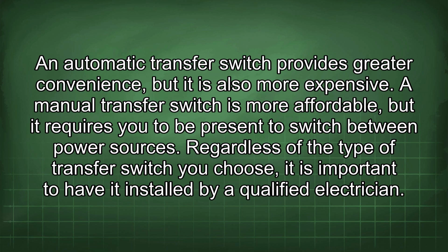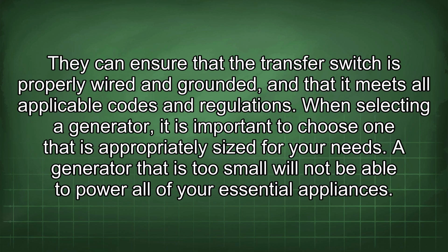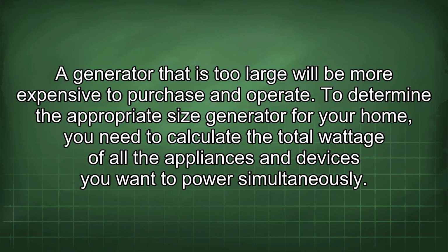Regardless of the type of transfer switch you choose, it is important to have it installed by a qualified electrician. They can ensure that the transfer switch is properly wired and grounded, and that it meets all applicable codes and regulations. When selecting a generator, it is important to choose one that is appropriately sized for your needs. A generator that is too small will not be able to power all of your essential appliances. A generator that is too large will be more expensive to purchase and operate.